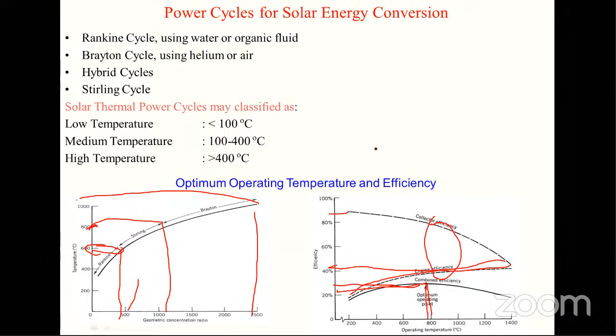Engine cycle efficiency increases with temperature, but a concentrating solar power plant combines the collector field with the engine. Combining these two gives an optimum operating point around 750-780 degrees, where efficiency reaches 35-36%. So a solar power plant operating at 700-800 degrees Celsius can give about 30 to 35% efficiency depending on pressure parameters, which is the same as conventional coal-based power plants. The solar power plant is as efficient as coal-based power plants.